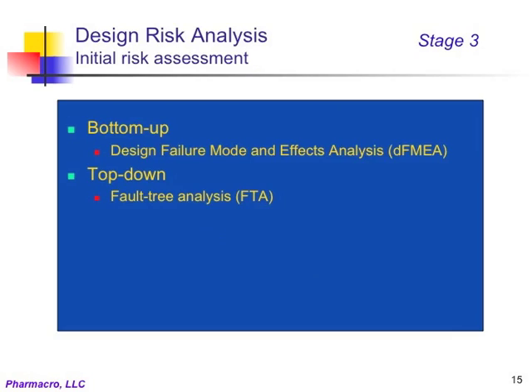A part of design plan is risk assessment, which includes both bottom-up and top-down risk analysis. In the bottom-up process, also known as Design Failure Modes and Effects Analysis, or DFMEA, each device component is considered independently, and the consequence of failure of the component on the performance of the device is evaluated and given a ranking based on the probability of occurrence and the severity of the effect on the performance. This process helps to identify high-risk areas which then can be addressed by making the design robust so as to mitigate the risk.